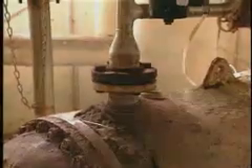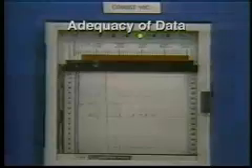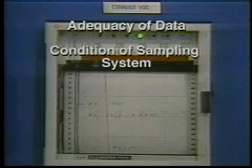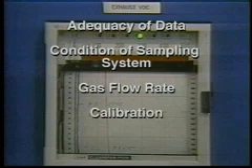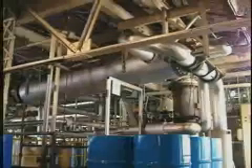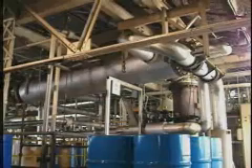The most direct measure of the performance of a condensation system is the organic vapor concentration in the outlet gas stream. However, most condensation systems do not have permanently installed analyzers. If there is an analyzer, the adequacy of the data should be checked as part of the overall performance evaluation. This would include an inspection of the condition and integrity of the sampling system and a check of the sample gas flow rate. In addition, the calibration frequencies and procedures and the maintenance records of the instrument should be checked. Calibration should be performed on a daily basis using a calibration gas cylinder that is less than six months old and has a pressure of at least 150 PSI-G.